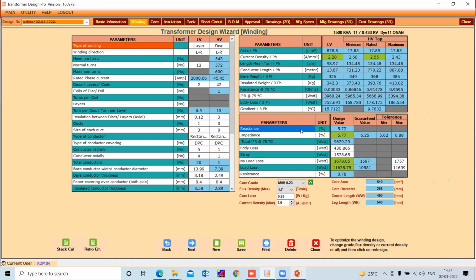Here you can see the reactance in percentage, the design value, the impedance. We have chosen on the basic parameter page the guaranteed value of 6.25. With the tolerance, it comes to 5.62 to 6.88, and the software designed this particular transformer at an impedance of 5.77. This software is such an intelligent one, friends, that it will choose not to work at the extreme levels, but will give a tolerance of 2 to 4%. That is nothing but the manufacturing tolerance based on these designs when you go for the manufacturing of the transformers.